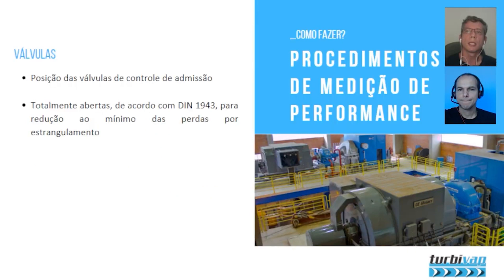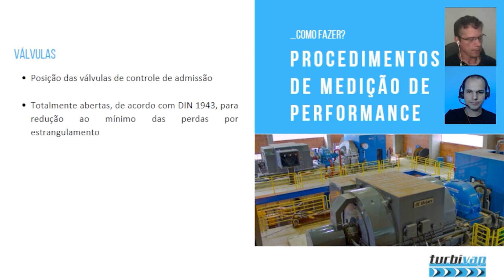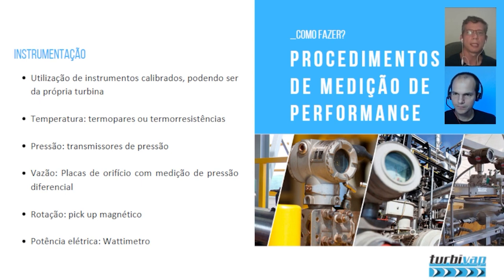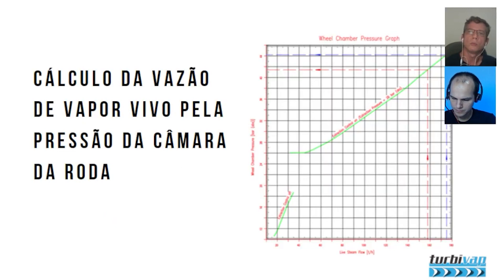Instruments must be calibrated and can even be those of the turbine itself. It is often useful to have a wheel chamber pressure versus intake flow curve, which allows us to determine turbine flow as a function of wheel chamber pressure. This is important because we often find inconsistent measurements from the system flow meter, especially for steam flow measurement. This ends up being a useful trick to have a second flow measurement reference.